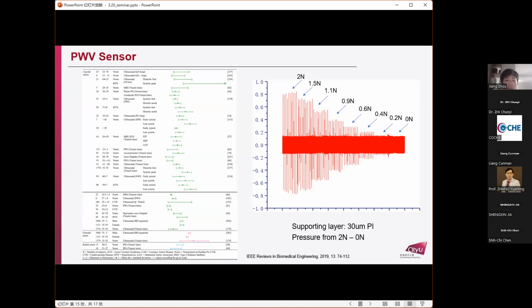Here's a table of local PWV from different places of the human body. From this data we can see that our pulse wave velocity test result is okay. The right picture is a characterization of our device. We use a 30 micrometer PI as a supporting layer, and this shows that our device has a very nice response to linear pressure force.